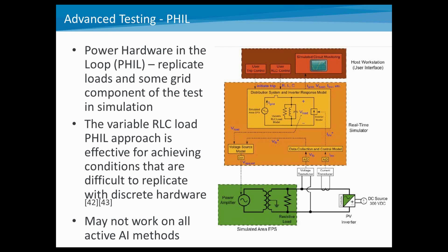What this allows us to do is not use a physical load bank, but actually simulate the load bank conditions. There are some references on this particular type of testing, but we were able to replicate and validate the tests that we typically do in full hardware with the ability to replicate that in software. It also allowed us to much more finely tune these resonant tank circuits. We were able to show that using these simulation approaches we could replicate the anti-islanding tests and results. One of the drawbacks is that it may not work on all active anti-islanding methods, because a variety of different anti-islanding techniques may use the load as a reference point.